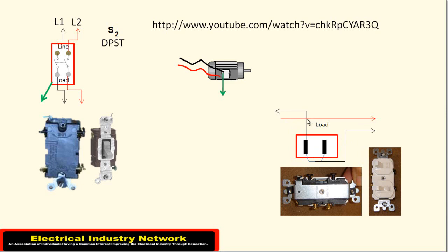If you follow along with that, basically this one was feeding straight through that J-box and it was unswitched. So it went in and then back out and it came back. If a service guy's out there working on that motor, only one of these is switched, and that's extremely dangerous. I'm not going to get into all the codes on all this right now, but I just wanted to do an overview of why you need to use a double pole switch on a 250 volt swimming pool motor. I hope that maybe clears up a few things if you ever go to change out a pool pump motor.